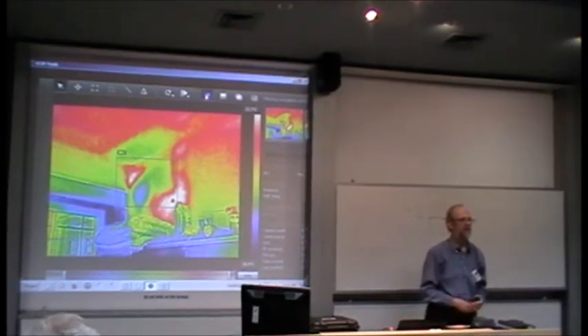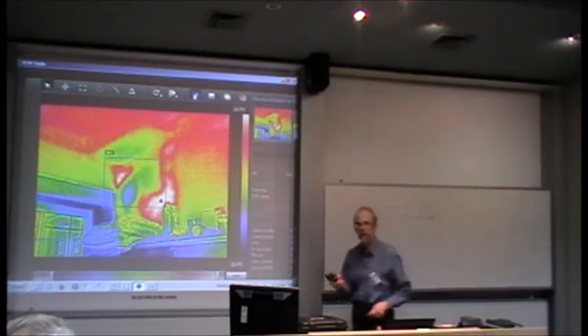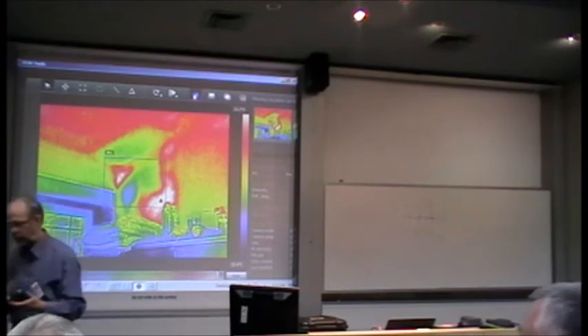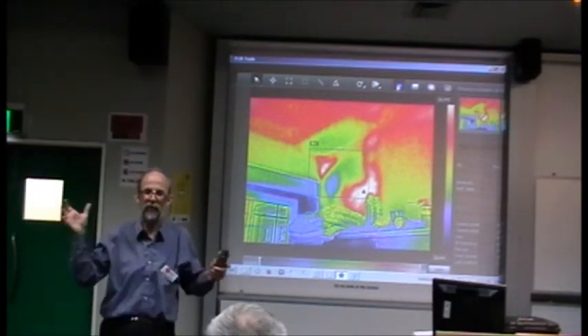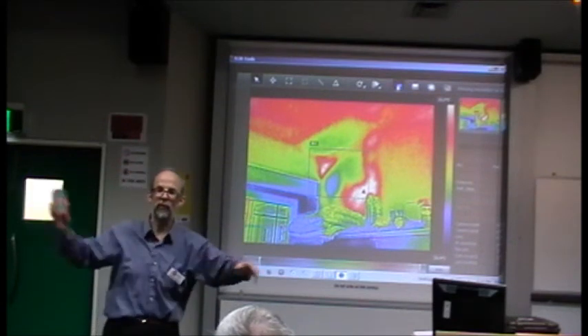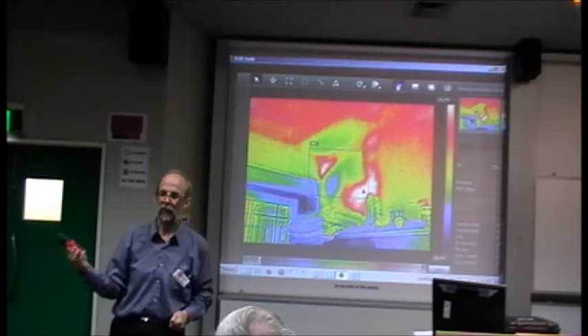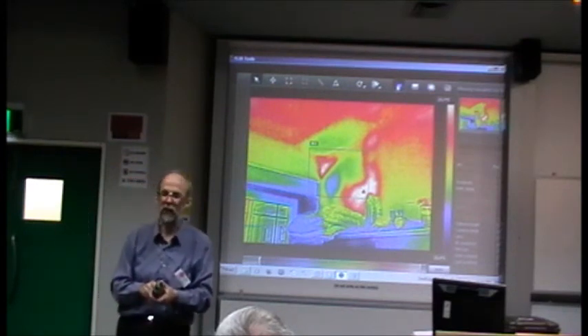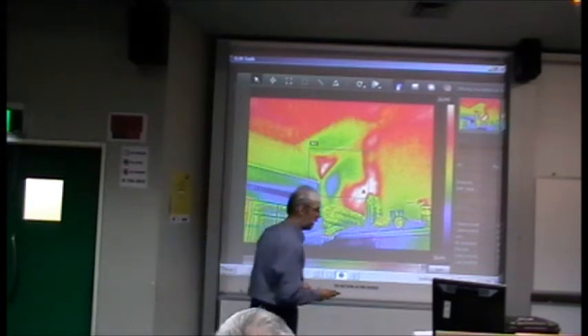Peter, I think I owe you a thanks there. This means that my spot gizmo, for which the spot has failed, is not as useless as I thought it was. So the thing with those is to get close all the time? Well, that's what you need to do. This one is actually quite bad. You can buy them where they are just what they call an infrared thermometer, and it's a really misleading term, because first of all, I can't make adjustments that I can make on this one to allow for the different materials, different reflections, so it's going to be wrong anyway. But some of the ones you buy which are just the infrared thermometer often have a narrower beam than this one. This 1-to-8 is dreadful. Some have two lasers, so you get an idea. Some of them have a ring of them, even, trying to give you some idea. And they're not so bad, because at least you know what you're getting.